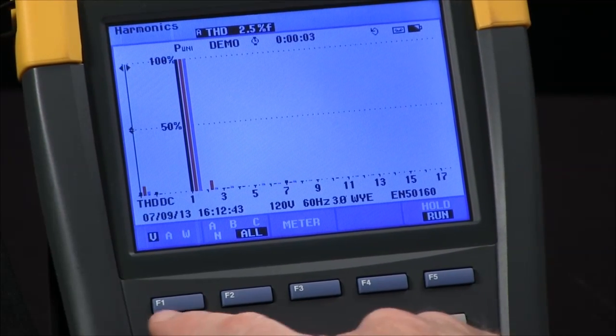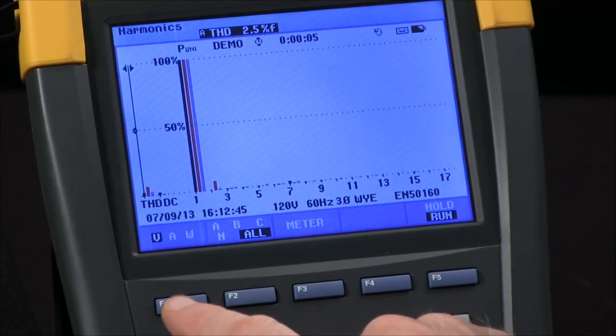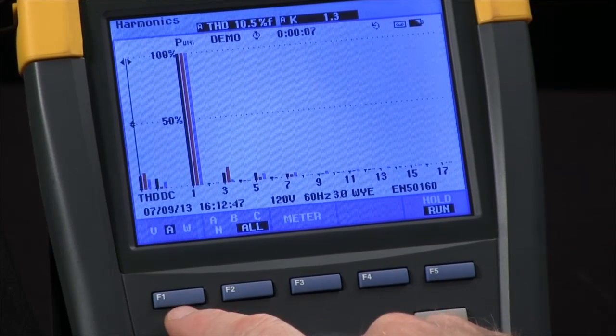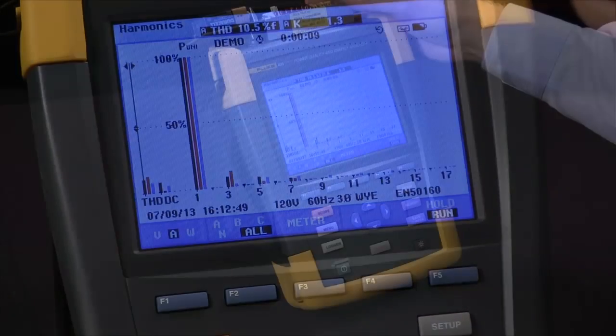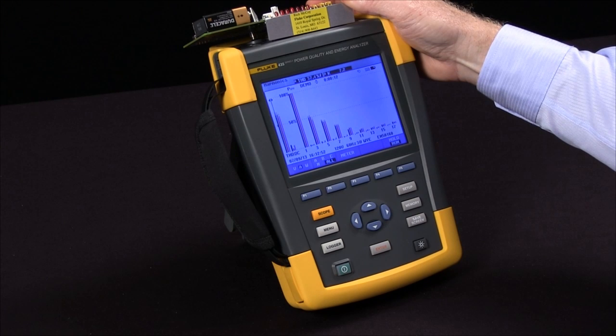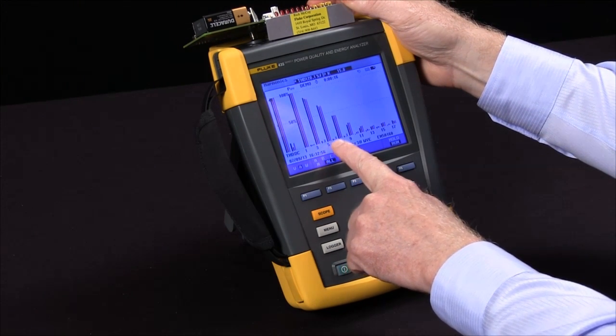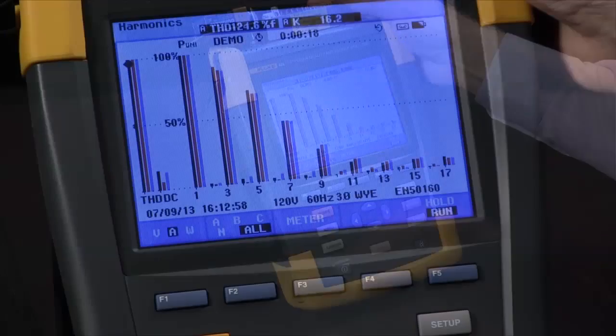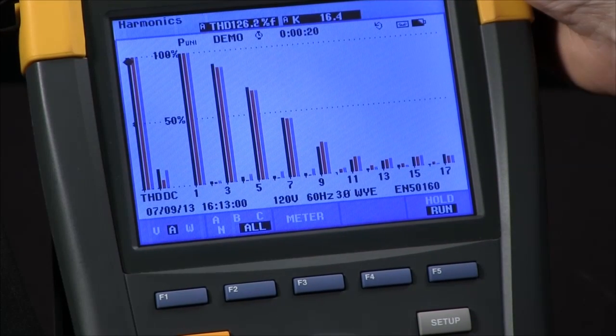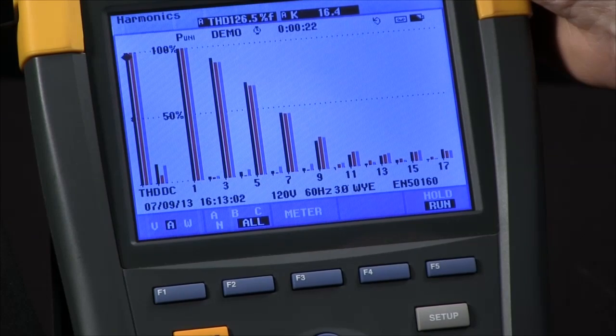Most harmonics are going to show up in amperage, so I'll use the F1 button to toggle the amps and generate some harmonics. In this case we can see that the third is the most prevalent, followed by the fifth and the seventh, indicative of a single phase power supply.